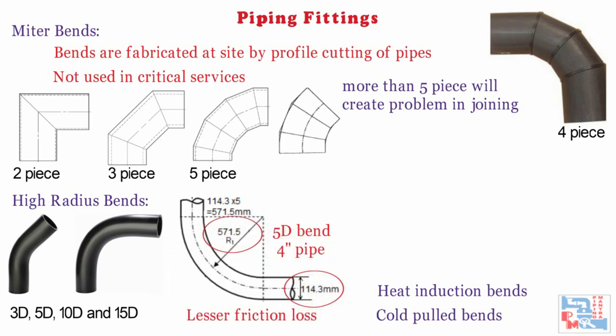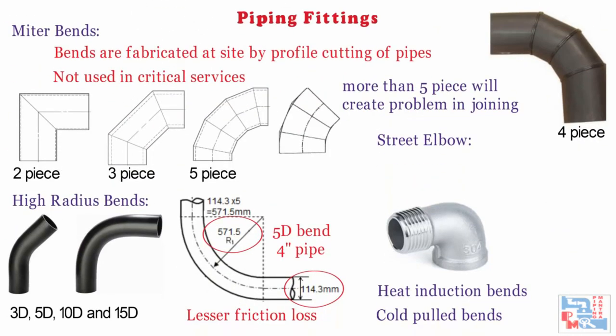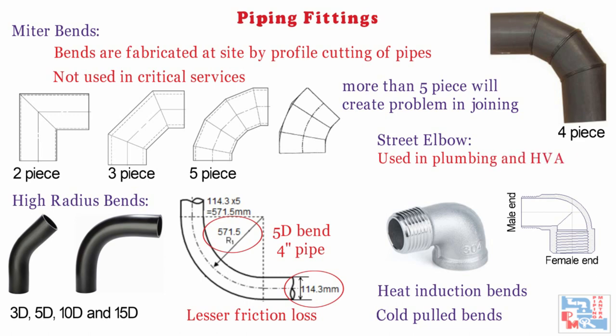There is one more type of elbow: the street elbow. It is the same as any regular elbow, but the difference is the gender of the two end connections. A regular elbow has a hub or female connection on both ends so that it can join two male-end pipes. However, a street elbow has a female fitting at one end and a male fitting at the other end. It is mainly used in plumbing and HVAC applications, but is not permitted in industrial piping as it makes pipe alignment difficult.